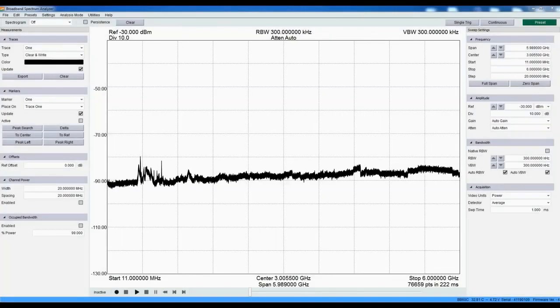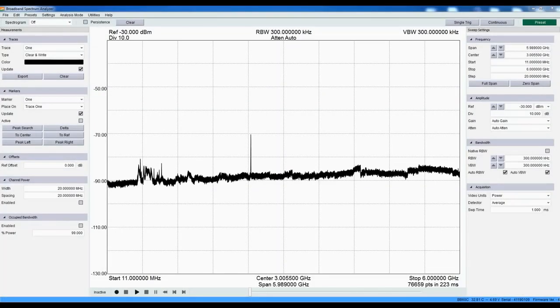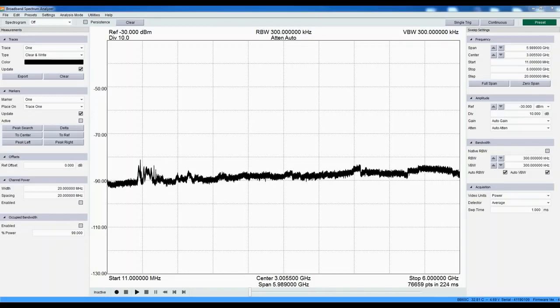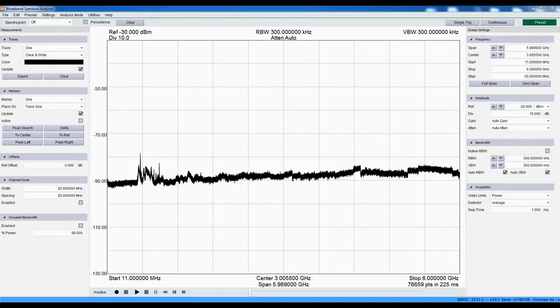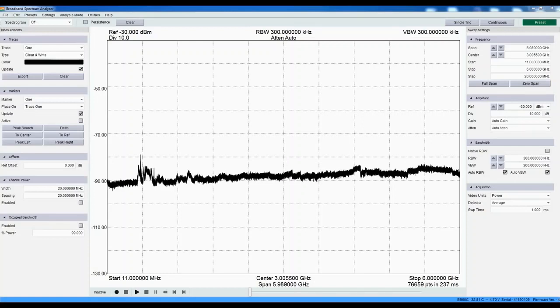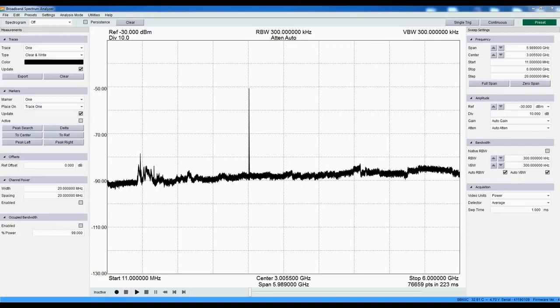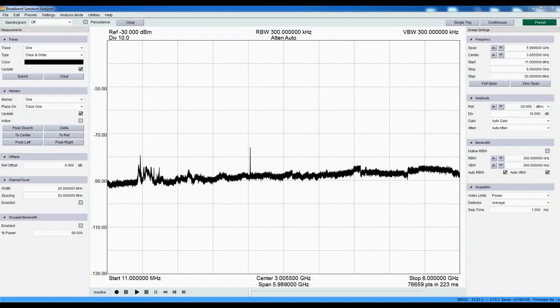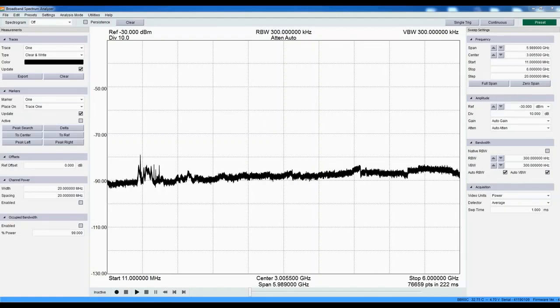Now I have launched the software. The device is sweeping the default span of 11 MHz to 6 GHz in about a quarter-second. The fast sweep speed of the BB60C lends itself to high probability of intercept interference hunting and EMC pre-compliance.